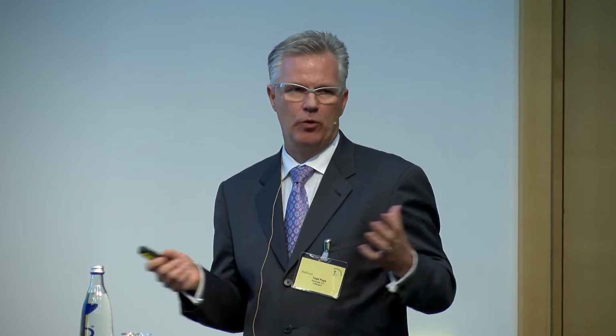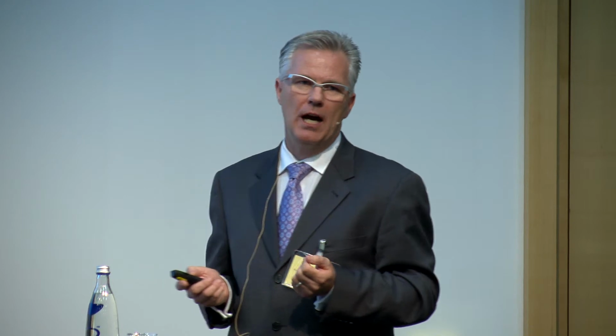Again, coming from the perspective of technology integration, we're looking down a hole. We need to put some kind of illumination into that hole in order to be able to see. The whole thing is predicated on light. And these image sensors translating a light signal into an electrical signal. The standard right now is a xenon-based light source. Has some drawbacks in terms of the heat that it produces, does provide very bright light, of course, but light-emitting diode technology has found its way into the light sources that are used now, so LEDs. They're efficient, long life, and inexpensive compared to xenon lamps.